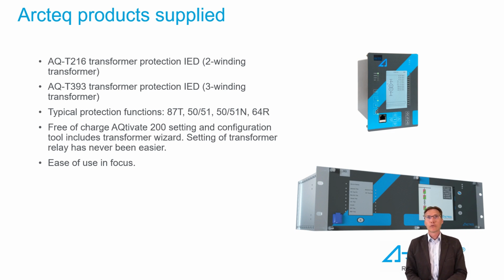Transformer protections, again applied in the second phase of the project, included the 2-winding and 3-winding transformers, with typical protection functions: differential, overcurrent, earth fault protections, and restricted earth fault. Here, like in all Arcteq products, ease of use is in focus, and our free of charge setting and configuration tool also includes a transformer wizard, which makes setting of a transformer from the nameplate values easier than ever. Very useful tool. You can download it from our website.